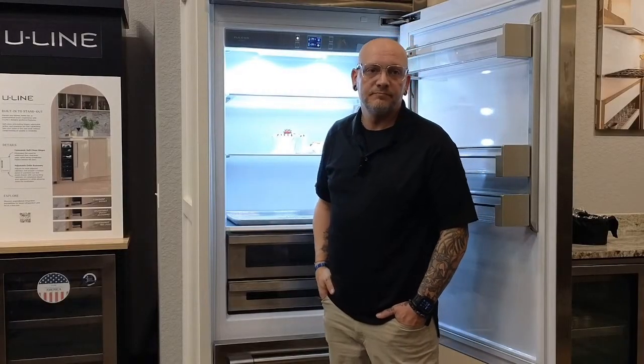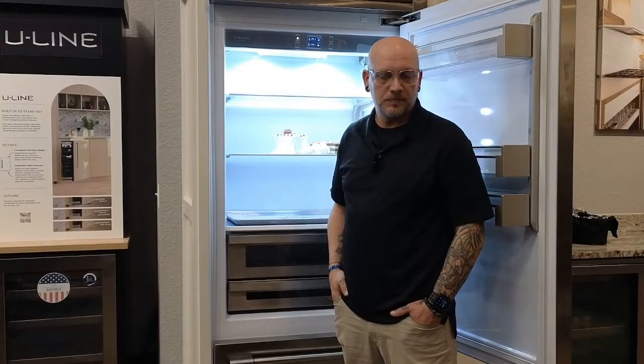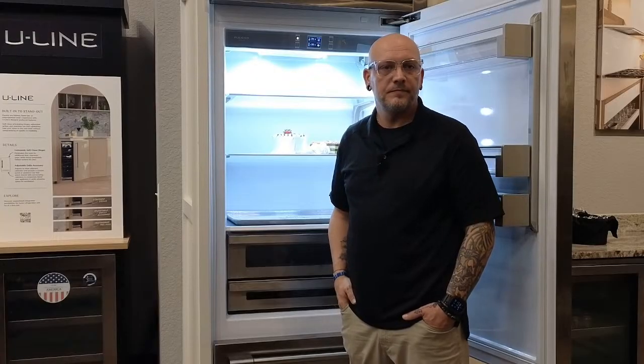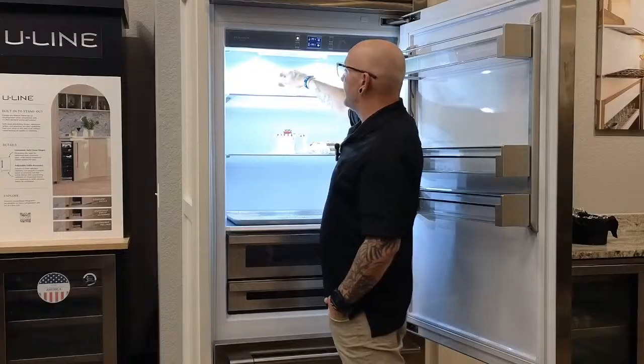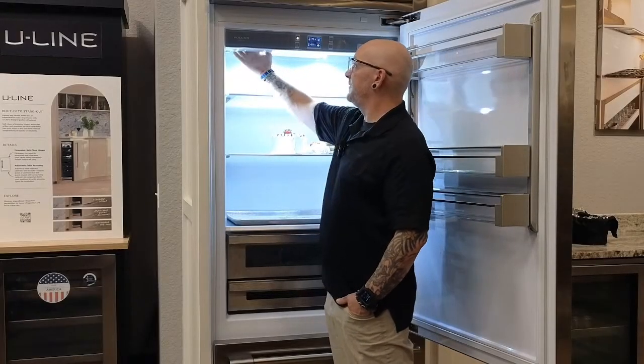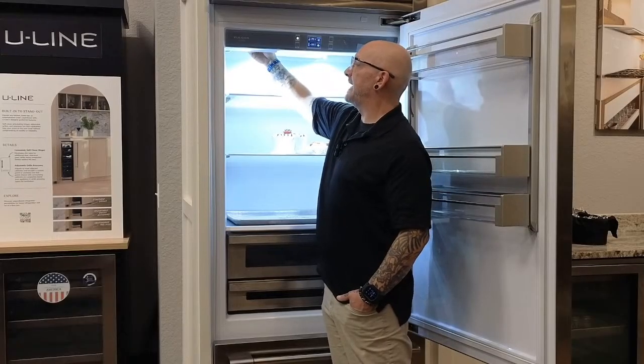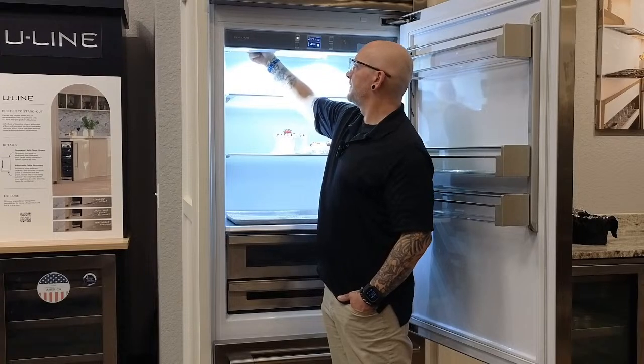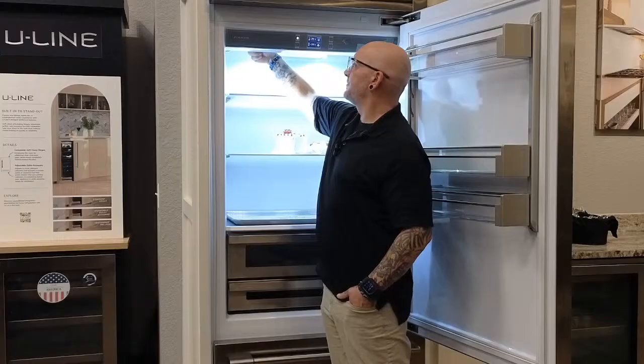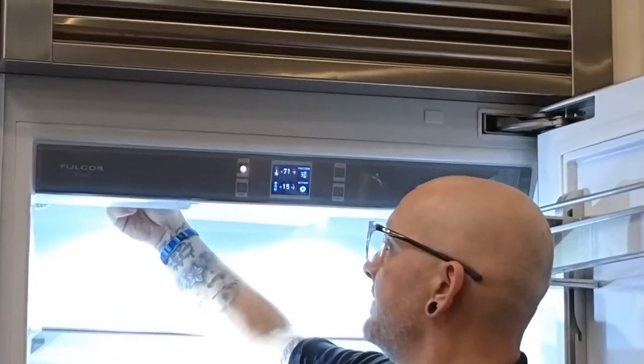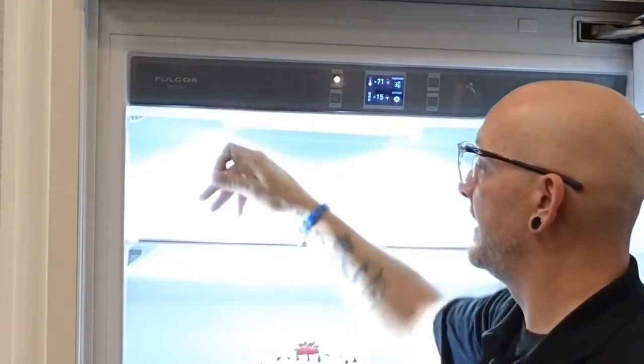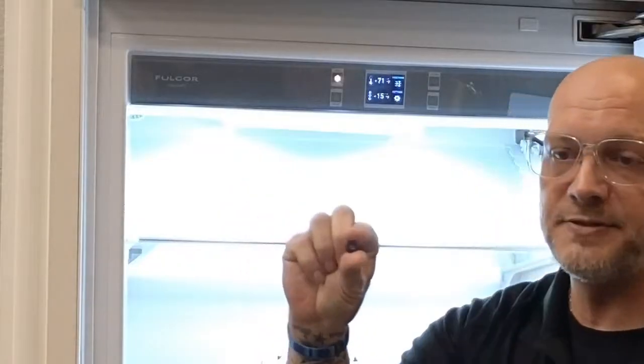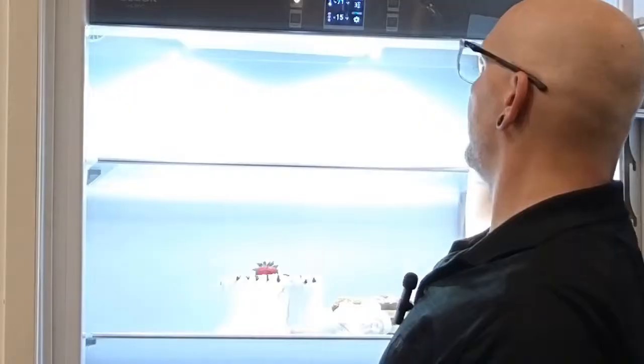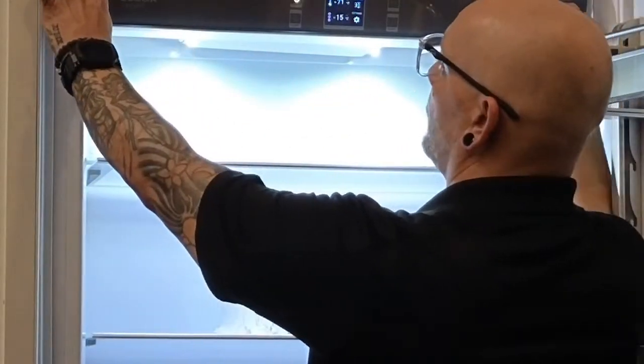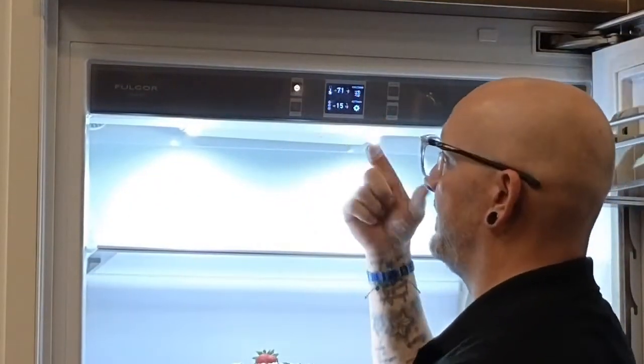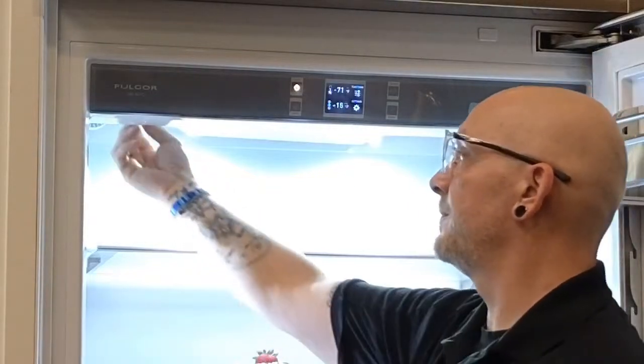So, Mike, a question for my servicers out there, just really quickly, if you can give us a little detail. If the user interface isn't responding or it needs to be replaced, how do I remove that user interface? Very easily. Great question. As you take down this top section glass, if you feel behind here, there are a couple of little wing nuts, little plastic threaded nuts. I'll pull one off and put it up close to the camera for you. There's plastic thread going through the front side, through the actual top here, and then you've got these little plastic thread certs that thread onto them, and there are three. There's one in the middle, one on the right, and one on the left. Once you remove these little black nuts, this whole display piece will come off, and your display will be mounted right to the back side of that. It's a very simple repair.